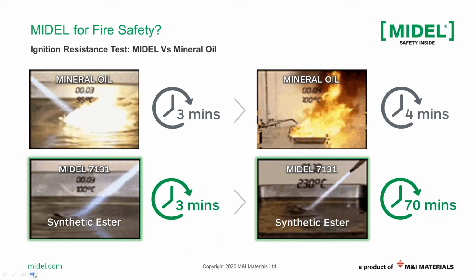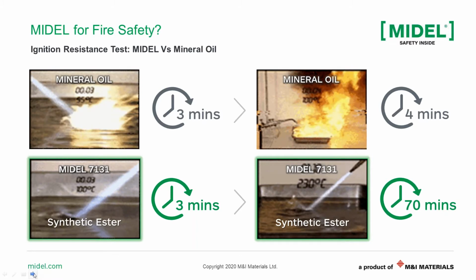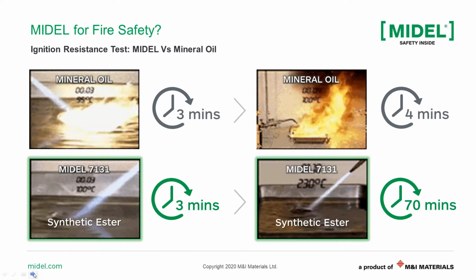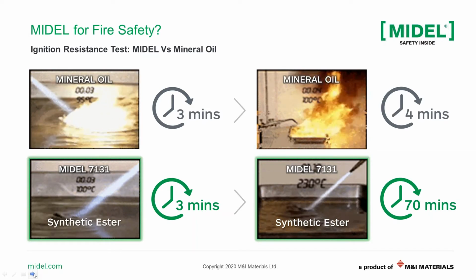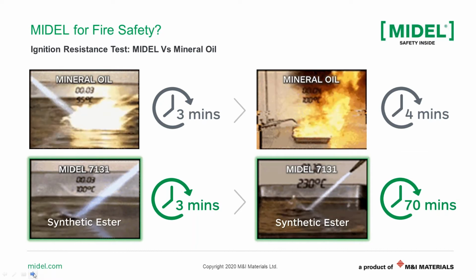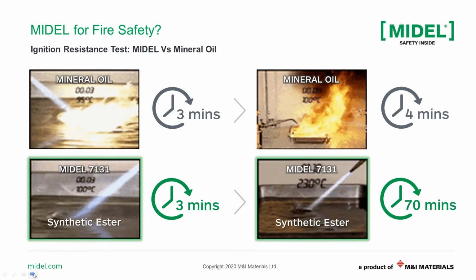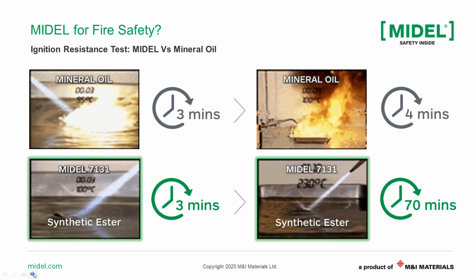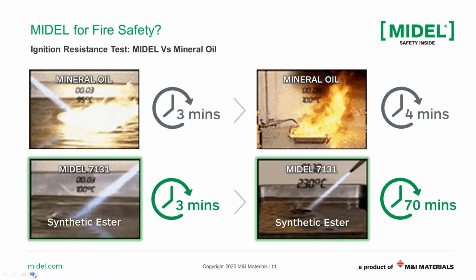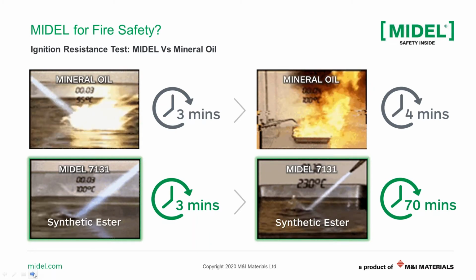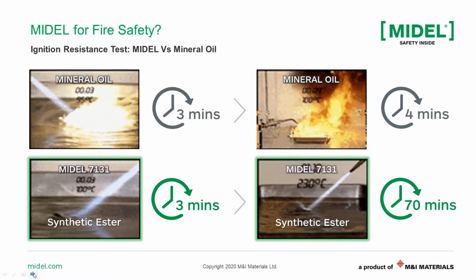On the bottom part you can see the MIDEL 7131. In this one, using the same 3000 degrees oxyacetylene torch, after 3 minutes you can see that it is just blowing the surface, and the temperature of this liquid is around 100 degrees C. After 70 minutes, which is an hour and 10 minutes later, you can see that the temperature has increased to 230 degrees C. However, the surface is just blowing again, and you can see some small sparks. Due to the self-extinguishing properties of this liquid, it is very hard to get a full ignition, and that is why we always say it is very hard to ignite.